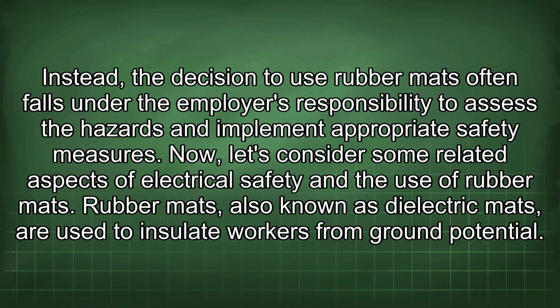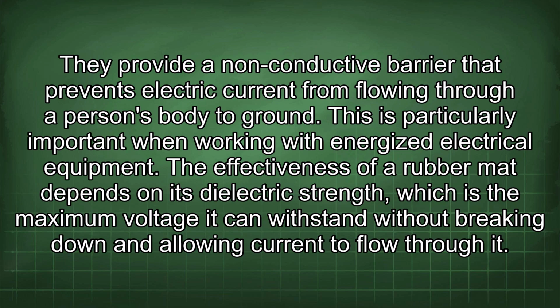Rubber mats, also known as dielectric mats, are used to insulate workers from ground potential. They provide a non-conductive barrier that prevents electric current from flowing through a person's body to ground. This is particularly important when working with energized electrical equipment. The effectiveness of a rubber mat depends on its dielectric strength, which is the maximum voltage it can withstand without breaking down and allowing current to flow through it.